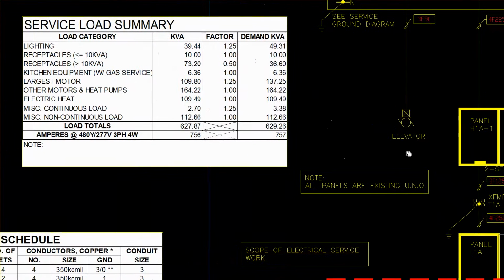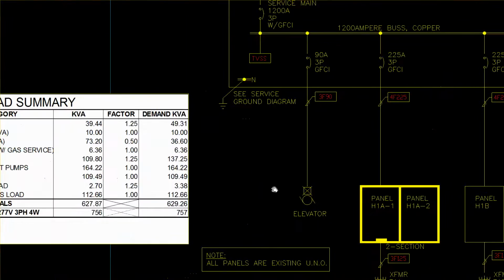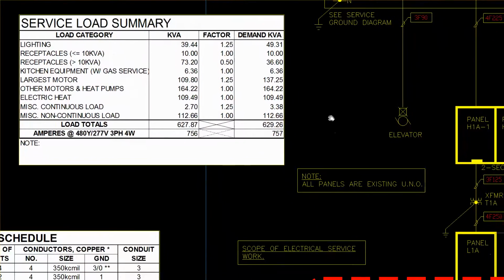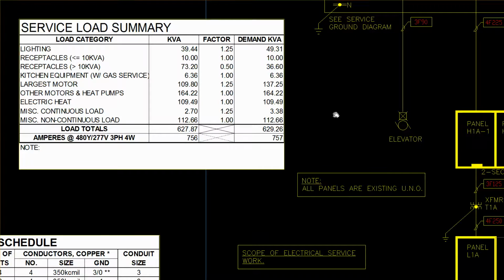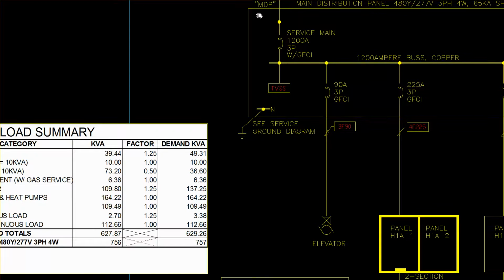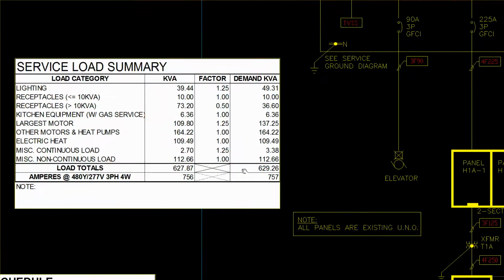And then another thing that's required is a service load summary. Sometimes there's a schedule just for the MDP. Sometimes, like in this particular case, there's just this service load summary, which we've created from our panel schedules, that tells us that on this particular 1200 amp piece of gear there's 757 amps. That's how that's being kept track of, this service load summary. If there's not a schedule for the main distribution MDP itself, then this is where that'll come into play.